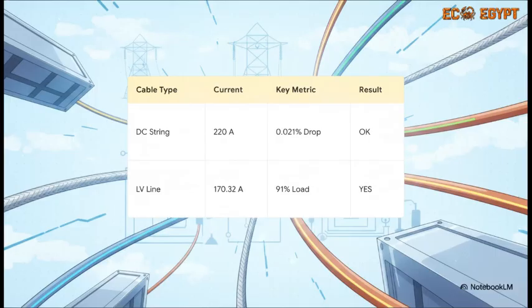When you distill all those massive engineering spreadsheets down, verifying the design really just comes down to simple pass or fail conditions. For example, our DC string cables pass with a microscopic voltage drop of just 0.021%. That is exceptionally efficient. Practically zero power is being lost as heat in those wires. Meanwhile, our 300mm aluminum AC cables are running at a hearty 170 amps, which puts their physical loading right at 91%. That safely handles the maximum continuous load, but sitting at 91% capacity means you are right in the sweet spot. You aren't wasting money over-engineering with cables that are way too thick and expensive.